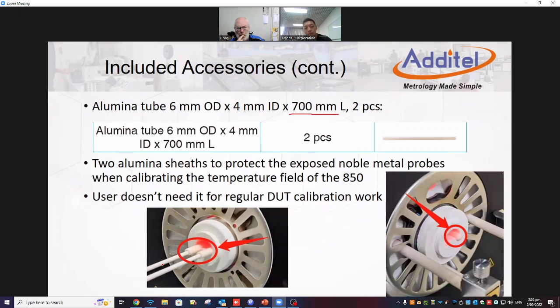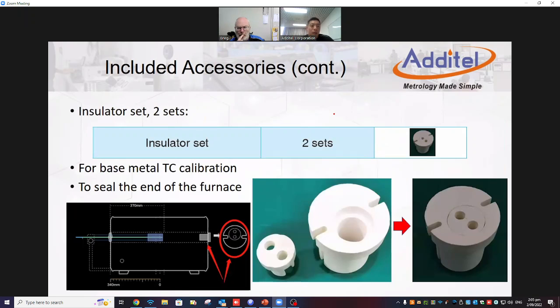Okay, so these two tubes, pretty long, 700 millimeters, are for the reference probe. Yes. The insulator, like this one, is the sealing to put on the inside of the furnace to reduce the heat leaking. Why is it designed like this? This is a little bit strange. This is because we can use this one to test the radial uniformity. One hole is always in the middle, and the other one is on the side. For the bottom one, you can rotate the entire insulator, so they can move the bottom hole to the top. This is to test the radial uniformity.